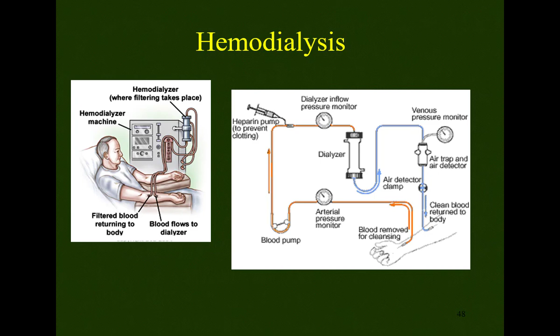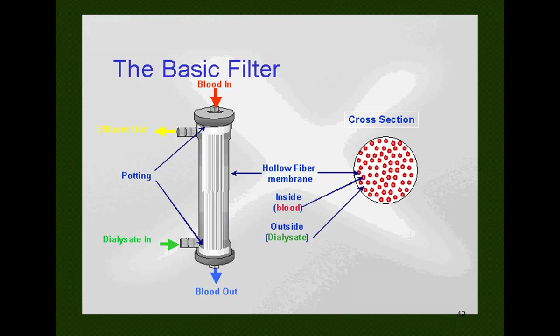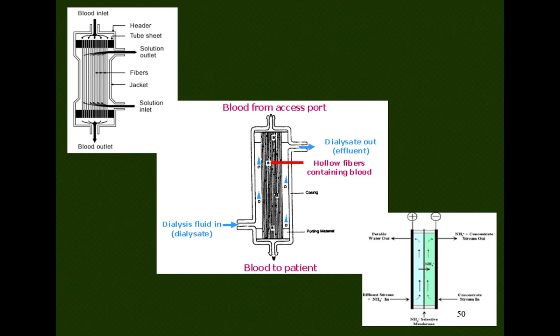Transmembrane pressure is the average of this pressure, the arterial head of the membrane and the venous head of the membrane. If this pressure is very high and this pressure is very low, what can be the possibility? Your membrane is getting clogged. The same principle we use in ECMO: before high, after low, that means something is problematic. In the filter there are so many small tubules, and the blood is running within these tubules, and the surrounding of the tubules is dialysate. What you are seeing in red would be blood, and what you are seeing in white would be the dialysate fluid. This is the one unit where the exchange is happening in terms of convection as well as diffusion.